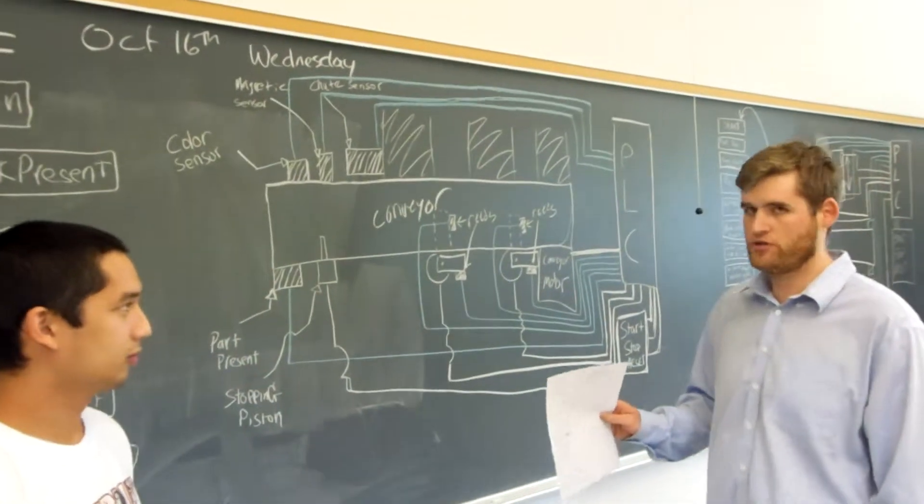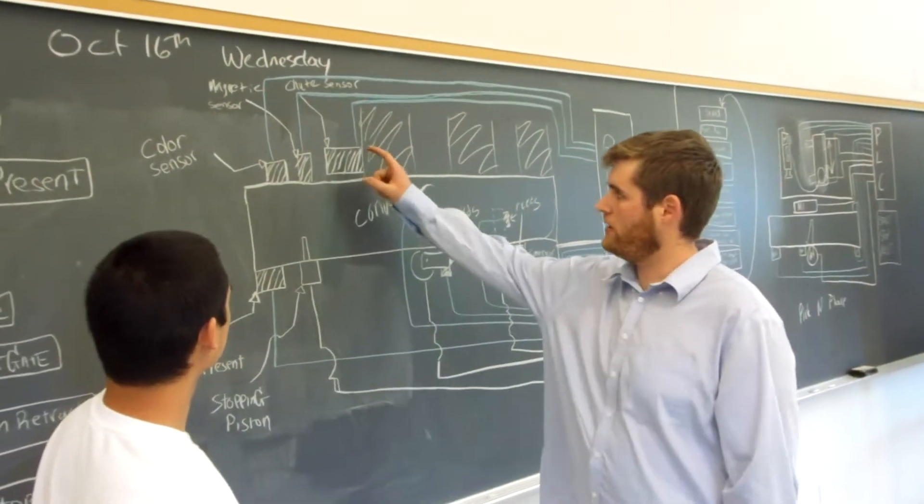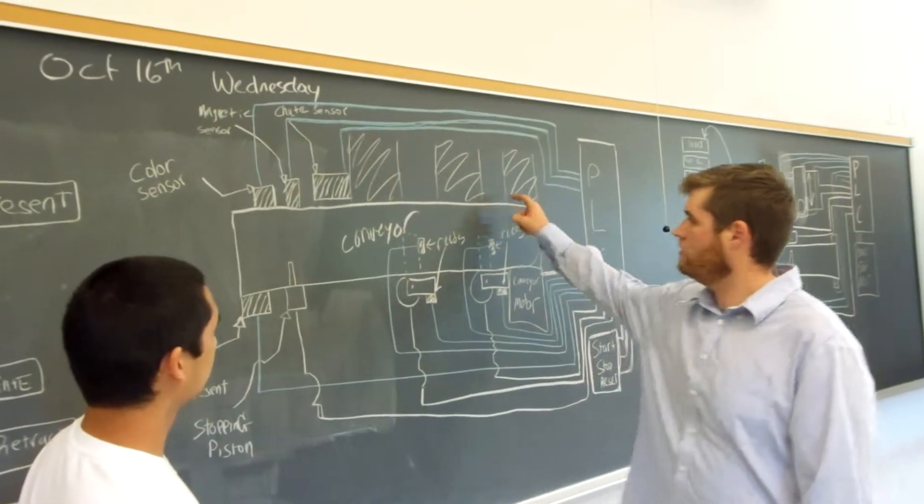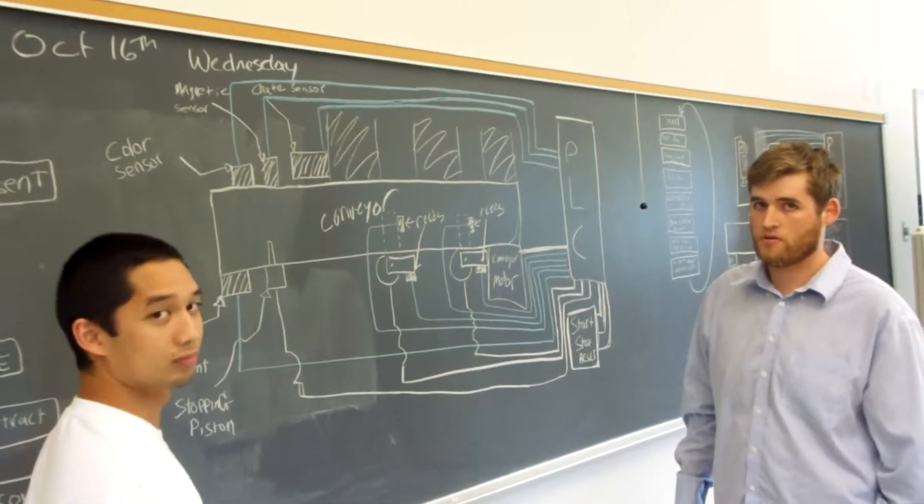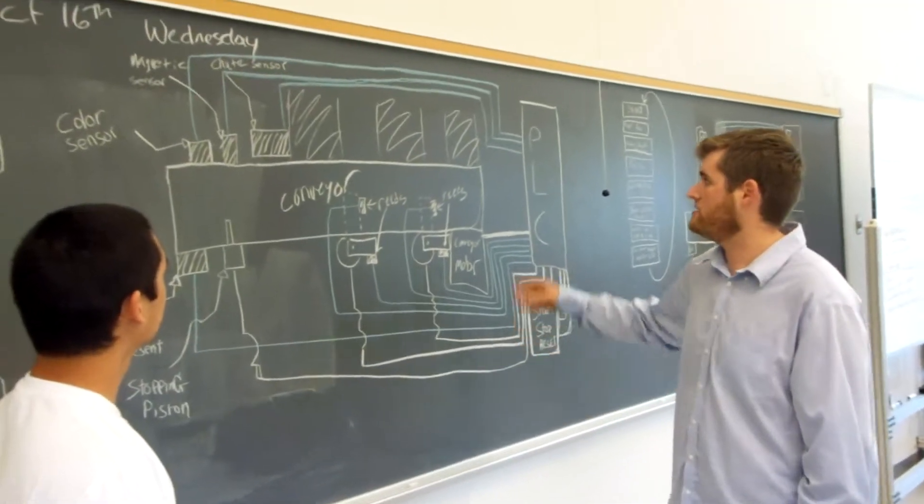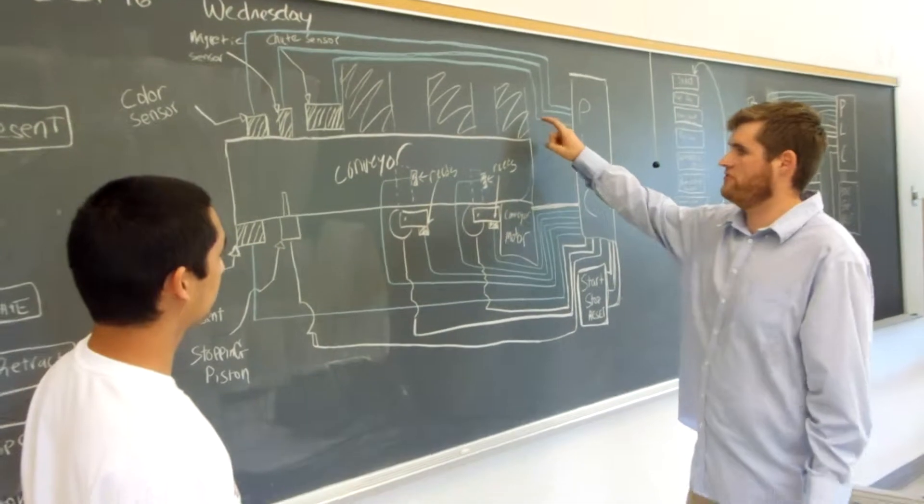It can both detect when an object enters the chute to restart the cycle, and it can also detect when a chute is full to stop. Okay, now I see where your chute sensor is there, and I see where your three chutes are. That chute, I'm guessing there's something else missing. The chute sensor needs a reflective, doesn't it? Yeah, it does have another piece here to reflect on the back, and that is missing from this diagram.